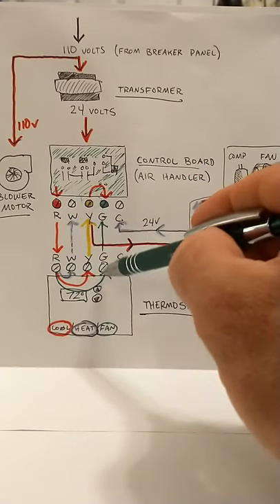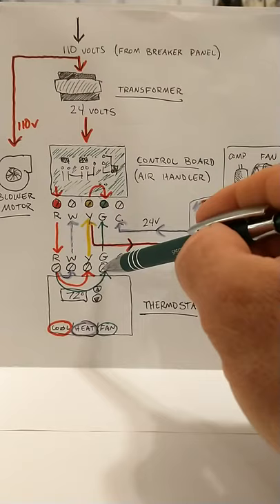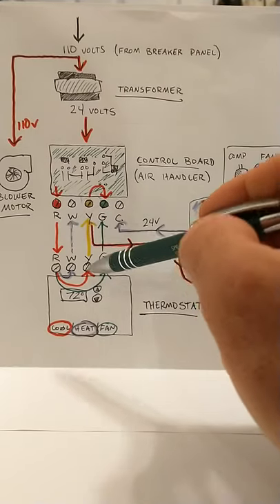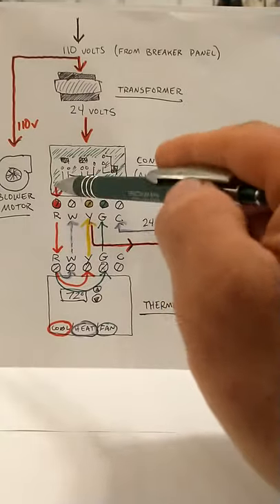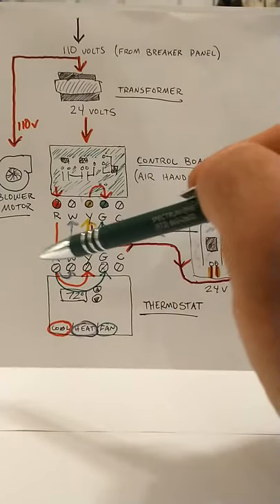Your 24 volts will travel from there to here. Your 24 volts will travel through the green wire from the G terminal in your thermostat to the G terminal at your air handler. And just the blower motor will kick in, circulating air throughout the house. And that's it.